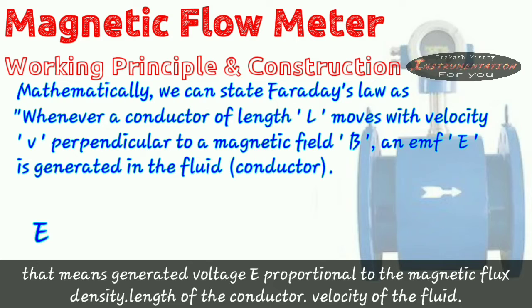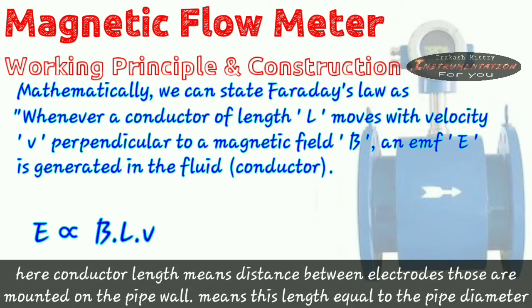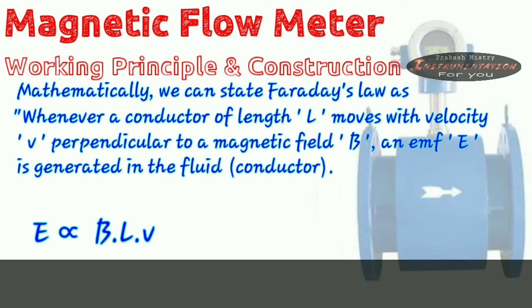That means generated voltage E is proportional to magnetic flux density into length of the conductor into velocity of the fluid. Here conductor length means distance between electrodes those are mounted on the pipe wall. This length equals to the pipe diameter.